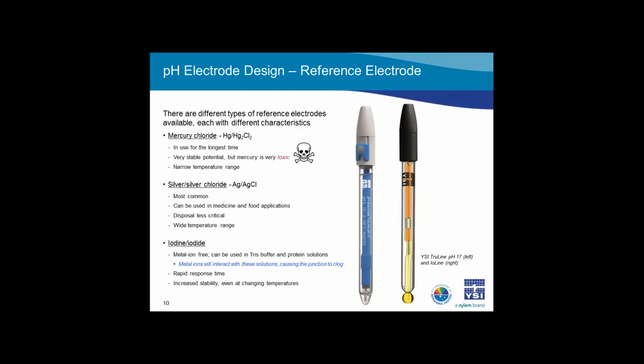Now, moving on to the reference electrode. There are different types of reference electrodes, but we will focus on 3 here. The mercury chloride reference electrode has been in use for the longest time. It has a very stable potential, but it is rarely used due to the toxicity of mercury. Also, the reliable temperature range when using mercury chloride is relatively narrow.